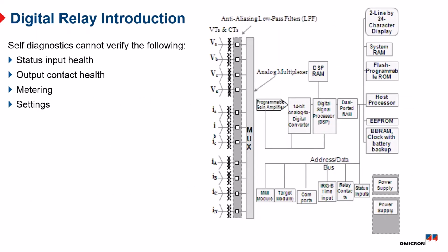Some of the things that the self-diagnostics still cannot monitor are the status inputs and breaker positions that come into the relay, which are now used pretty extensively in logic. Output contacts: it can't detect if an output contact is welded or failed. And most of these relays use a pretty light duty electromechanical contact. There's some solid state as well, but those relays were selected because of their high operating speed and small footprint and small power consumption and all that. They were not really designed to handle a lot of current. So sometimes if they're misapplied, or if there's a miswire somewhere, they can be pretty easily damaged.